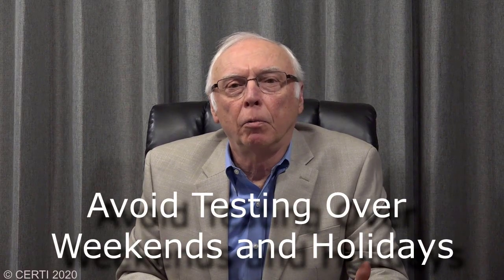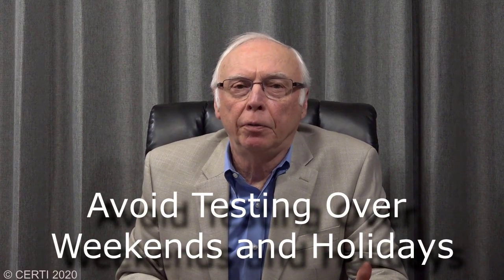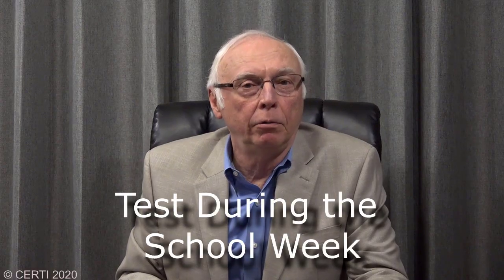One last aspect of an HVAC system controlled by an energy management system is that not only is the fresh air makeup reduced or shut off at night, fresh air makeup is also shut off on the weekends. The conditions that exist during weekends are not what students and staff are exposed to, and the results of a radon test conducted over a weekend, quite frankly, is meaningless. Unfortunately, school personnel and even radon professionals have conducted short-term tests over weekends to minimize disruptions. However attractive that may be, avoid testing over weekends or long holidays, as it may cause you to fix a problem that doesn't exist. Radon testing is unobtrusive and should be conducted during the school week.